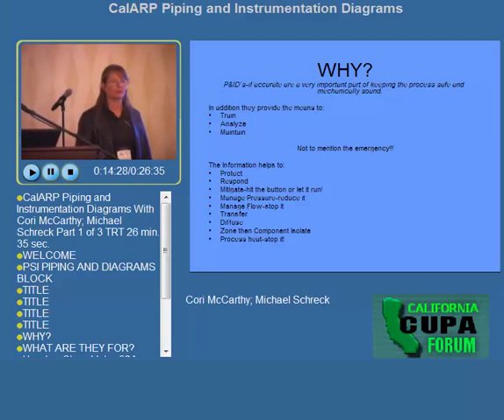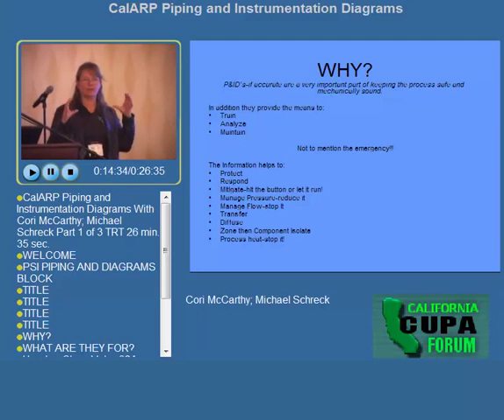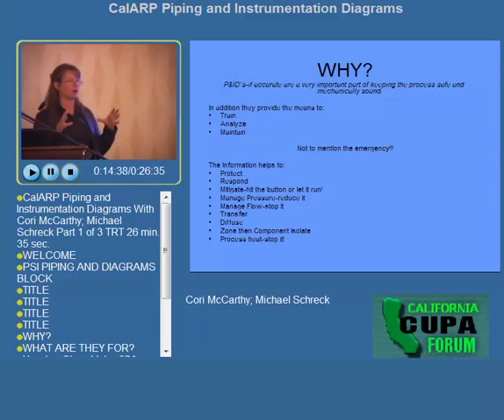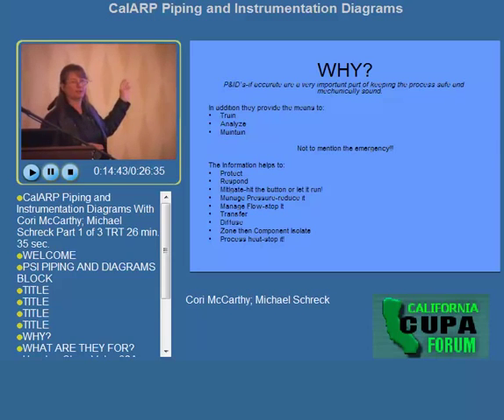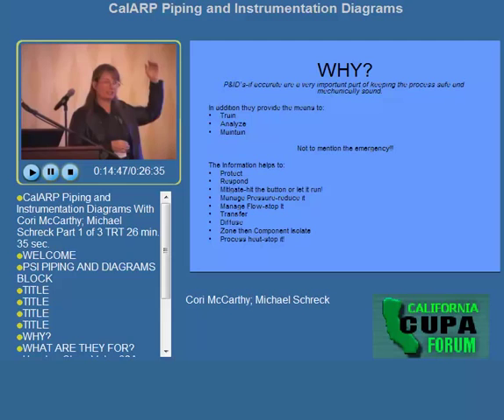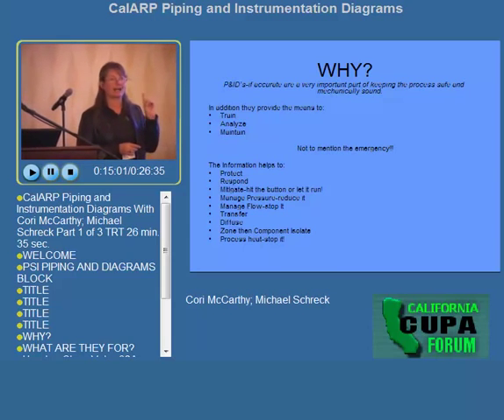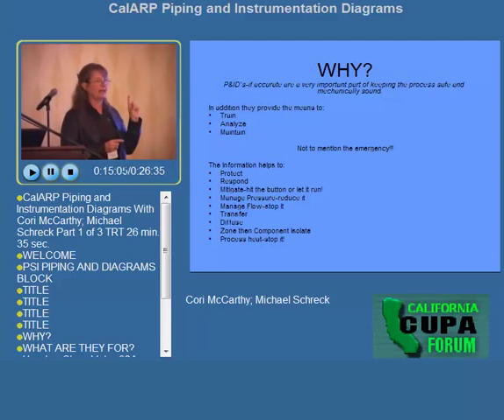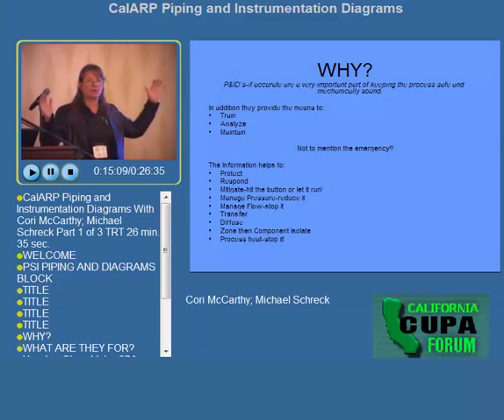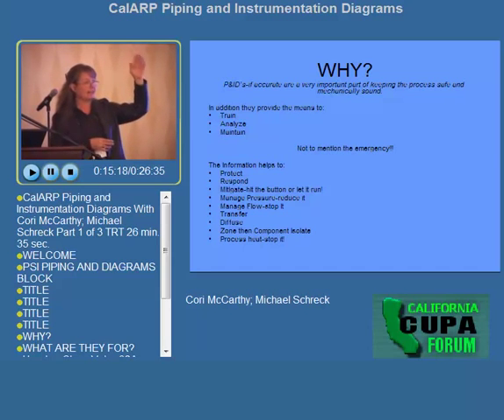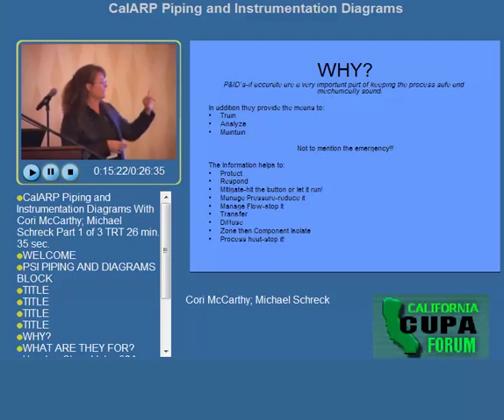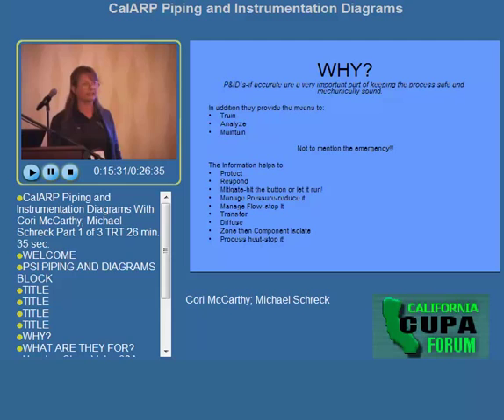How many of you are familiar with diffusion tanks here in California? We have a safe place to take all of our ammonia so we don't harm the community or workers. You have to decide whether diffusing is the best choice. We believe P&IDs are most critical for understanding how to isolate a zone — every box in a facility is a zone. We can close doors and keep ammonia inside a zone. But having outdated, incomplete, or unused P&IDs is of no use to anyone.